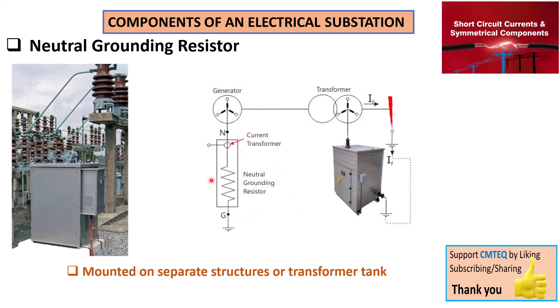It is important to note that the neutral grounding resistor does not protect against fault — it limits the ground fault. It limits the current to a safe value. That does not mean we should let the fault current just flow. We still have a current transformer, and despite having the neutral grounding resistor, we still want it to detect the fault current and send the appropriate signal for the circuit breaker to interrupt the line. Substation personnel will then send a technician to fix whatever caused the fault current to occur.